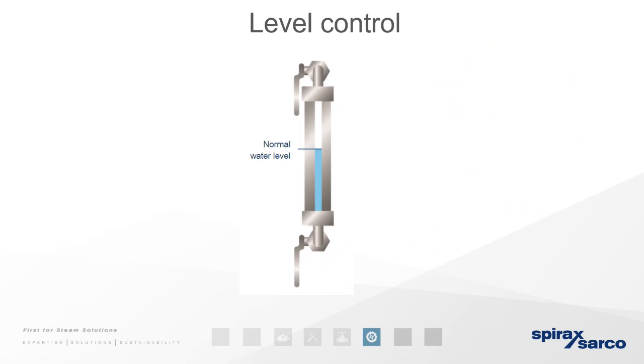Many of you will have seen that somewhere on your boilers there is a visual means to check the level in your boiler. Its purpose is to allow the boiler operator to have a very quick and reliable visual interaction with the boiler. So without having to check anything too difficult, he knows instantly when he walks into the boiler house how safe it is and the relative position of the water in that boiler.